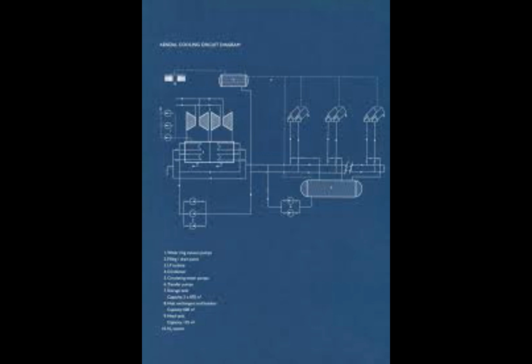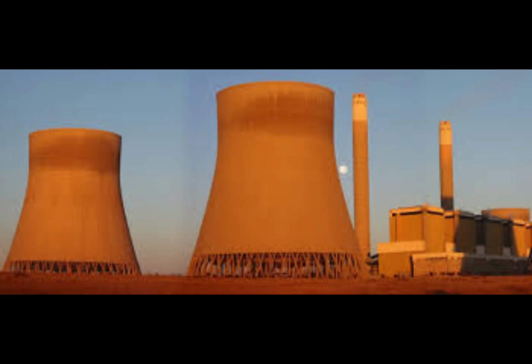The boilers are of the controlled circulation subcritical design, with coal-fired radiant furnaces and reheating. Kendal's turbines are of the tandem compound reaction type. The 2 chimneys are 275 m high structures, each having 3 internal brick flues, and their foundations rest on weathered bushveld granite. With a height of 165 m and a base diameter of 165 m each, the cooling towers are the largest in the world.